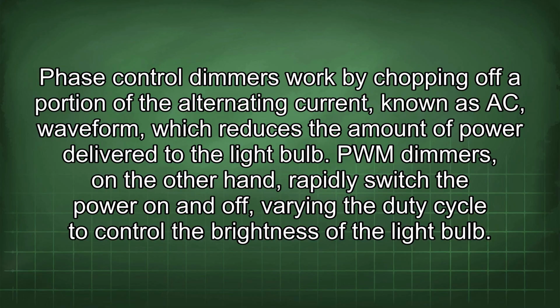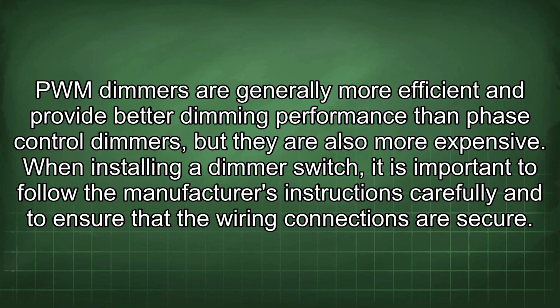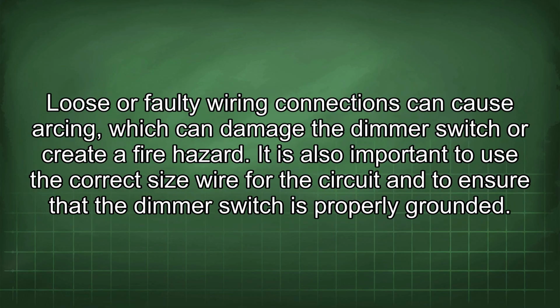PWM dimmers, on the other hand, rapidly switch the power on and off, varying the duty cycle to control the brightness of the light bulb. PWM dimmers are generally more efficient and provide better dimming performance than phase-controlled dimmers, but they are also more expensive. When installing a dimmer switch, it is important to follow the manufacturer's instructions carefully and to ensure that the wiring connections are secure. Loose or faulty wiring connections can cause arcing, which can damage the dimmer switch or create a fire hazard. It is also important to use the correct size wire for the circuit and to ensure that the dimmer switch is properly grounded.